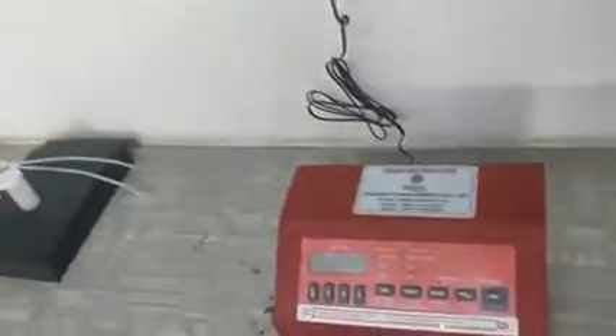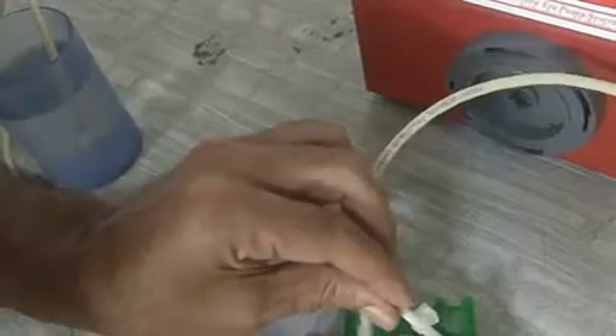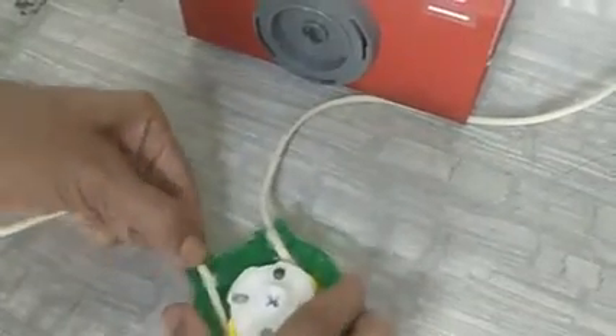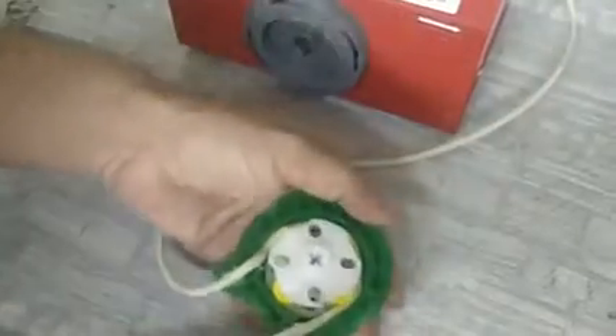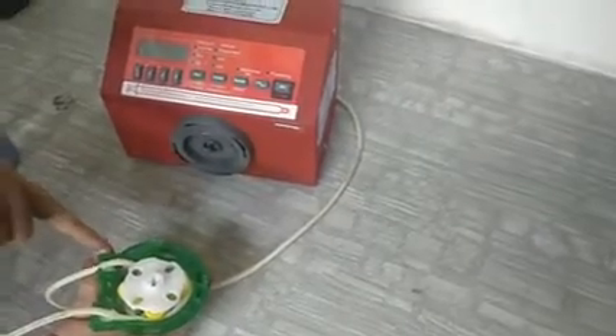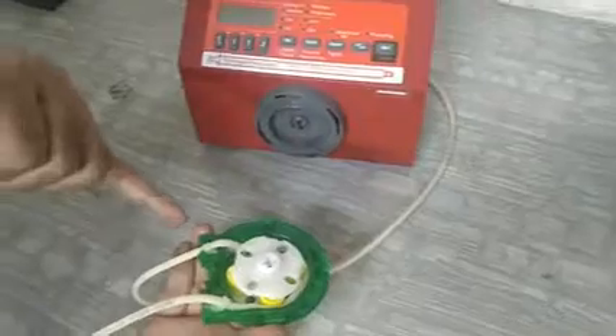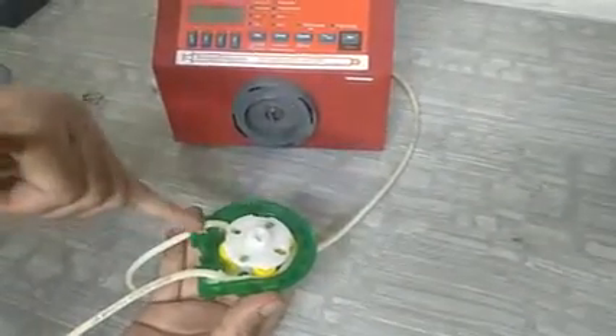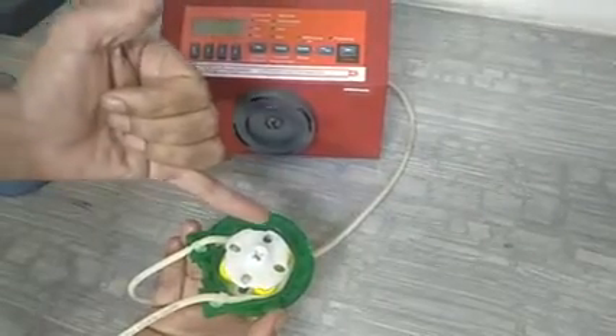So let us see how we connect this tubing into the head. Here we have already connected it actually. Otherwise you will see that there are 2 tie wraps. We will wrap the tubing around the rotor, and then in this socket we will push our tie wrap. So both the tie wraps will come like this, and this latches. The distance between the tie wraps is exactly 138 mm. This distance is important if you change the tubing later, otherwise the tubing will be loose on the rollers. And this head is a 4 roller head.